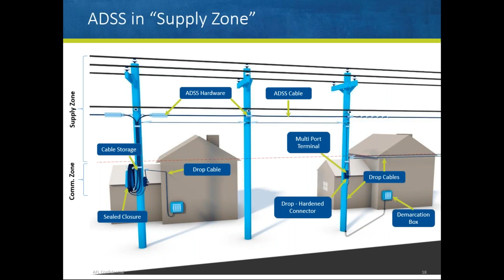This is preferred by many utilities so that, for ease of splicing, you don't need a qualified worker to be able to get into the supply zone to access the closure before splicing. Although that's not required, and if desired, the splice closures could easily be in the supply zone as well, just not attached directly to the ADSS cable, either to the dead end or to the back of the dead end. And then multi-port terminals with hardened connectors to attach to the home. In this case, you can see on the left drop cable going aerial, and on the right the drop cable going underground, and that's also a follow the power type situation where if power goes aerial or underground, the drop cable would follow it.